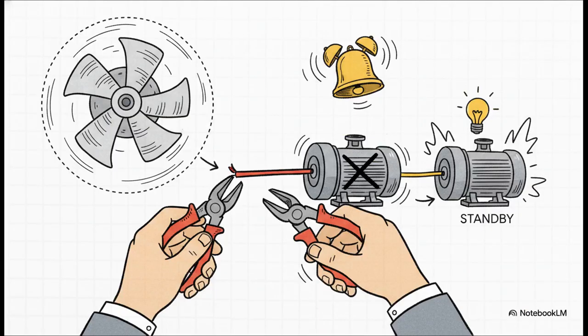To prove the system's resilience, engineers actually have to intentionally break things. They will physically cut power to a primary lube oil pump just to verify that the standby pump automatically roars to life. They'll simulate a sensor fault by, say, lifting a wire, just to confirm it triggers an alarm without throwing the entire turbine into a full emergency shutdown. The whole goal is to guarantee the safety systems catch a single fault and handle it with graceful degradation, keeping the plant safe and, if possible, online.